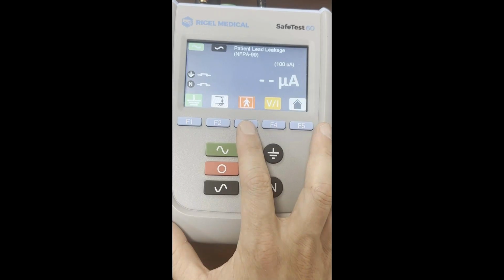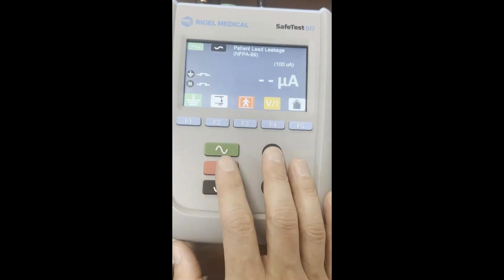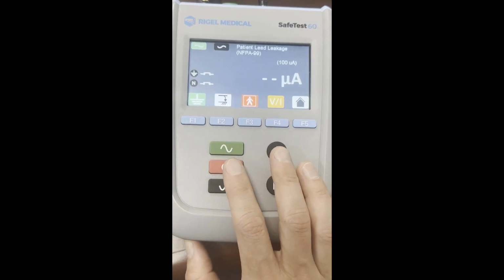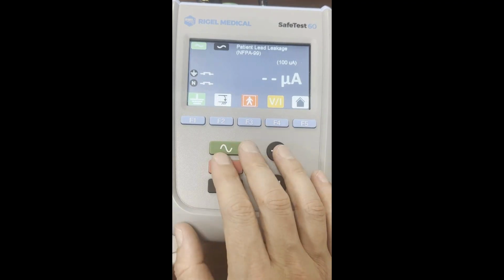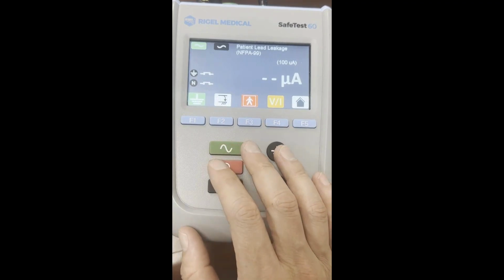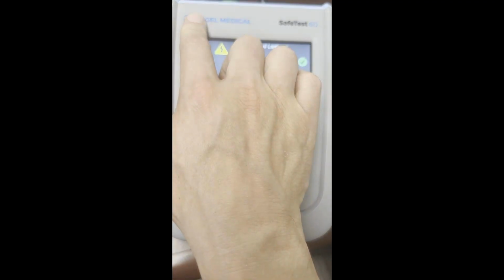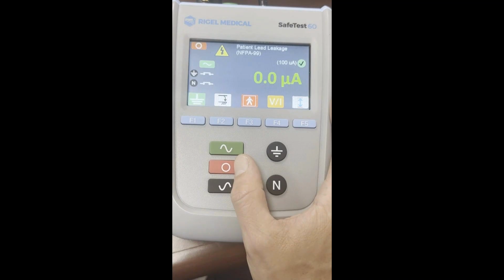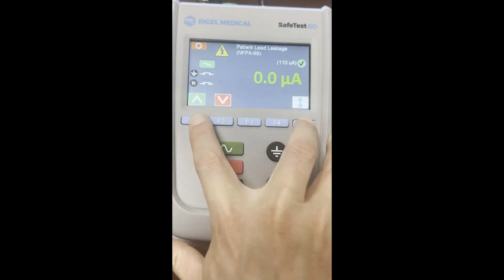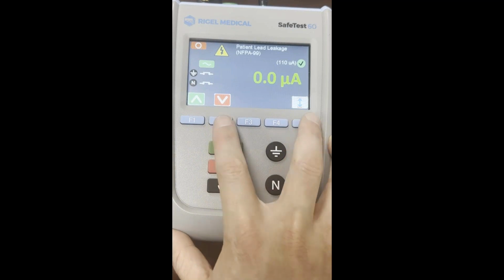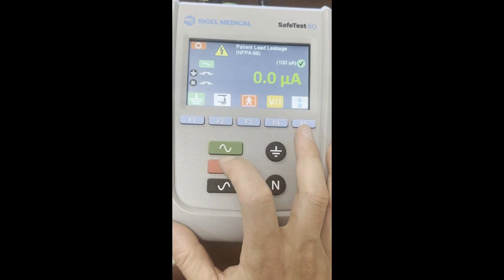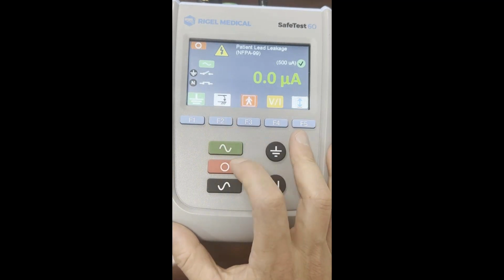Patient lead leakage is F3. We can see that when we switch the ground open and closed, it changes the limit. You need to perform two tests. Hit the green button to activate the output. As long as the value is below that, it's within specifications. This is reading very low levels, as you'd expect. You can change the limits if you need to, but it is default there when you switch the device on and off.